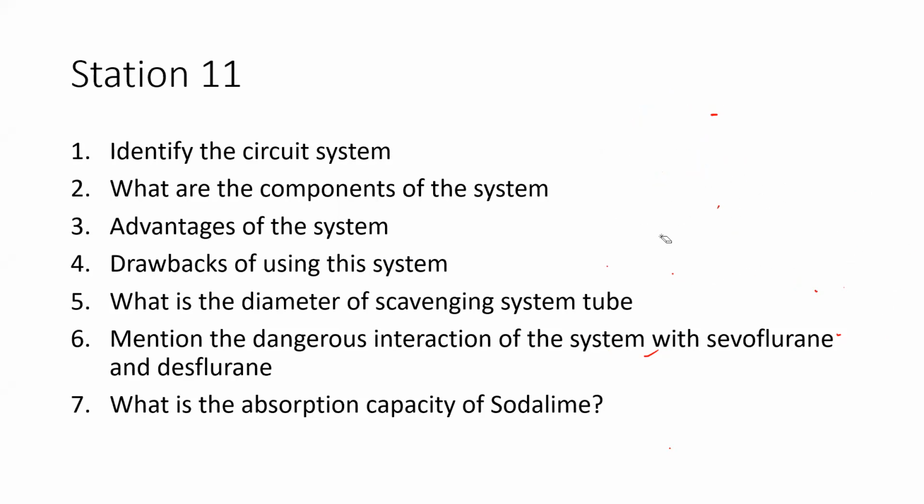30 millimeter. I said 30 yesterday, right? In anesthesia, the number 30 is the only place where you get it, the scavenging tube. It is made 30 mm because it is a passive scavenging system, so it can flow. When you keep a diameter wide, it can flow without any resistance. So that's why it's a huge tube.